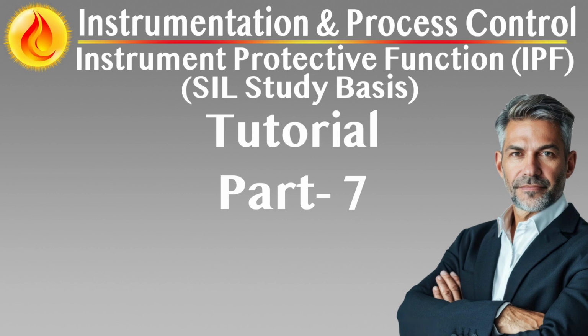Smoke detectors are typically used in enclosed spaces like control rooms, electrical cabinets, or HVAC ducts. Photoelectric or ionization types may be used based on fire development characteristics. All detectors must be certified for use in hazardous areas where applicable, with consideration for temperature class, ingress protection, and corrosion resistance.